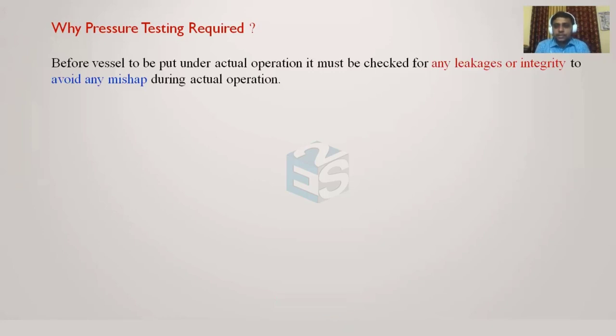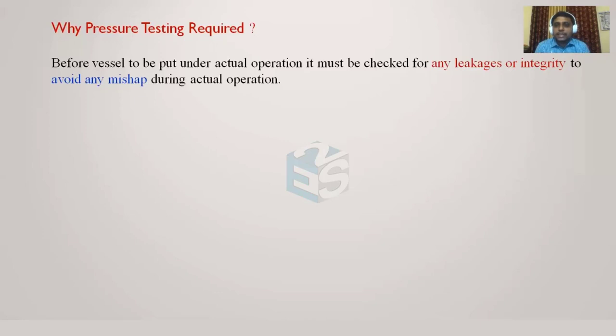If the vessel is in lethal service and there are any leakages that only come to light during operating conditions, it will already have leaked and people could lose their lives — a very severe condition. But if we test it prior and any failure is arrested at the hydro test condition and rectified, then by the time it is ready for actual operation it will be 100% okay from a pressure and temperature standpoint. This is how pressure testing is important — the vessel can be hydrostatically, pneumatically, or vacuum tested as applicable.